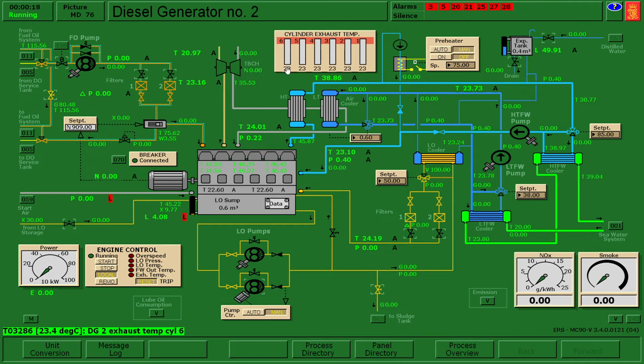Okay. So in DG2, we're gonna go ahead and close our discharge valve, and then we're gonna go ahead and open our makeup valve. And we're gonna wait until this reaches at least 45 liters. And while waiting for that, we're just gonna turn on our preheater and then set it to automatic mode. So we're gonna wait for this. Alright, that's already 45 liters, so we can turn that off. Now let's proceed to opening our lube oil filter number 1.